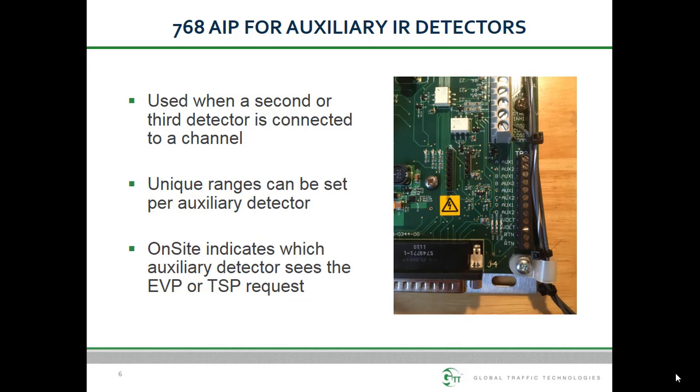It is also possible to see which detector is seeing an emitter signal on the current activity screen. The input column will indicate if the signal is coming in on a primary input versus one of the auxiliary inputs. The auxiliary detector connector also provides additional terminals for detector power and ground, but you may use the power and ground connections that the primary detectors are connected to.